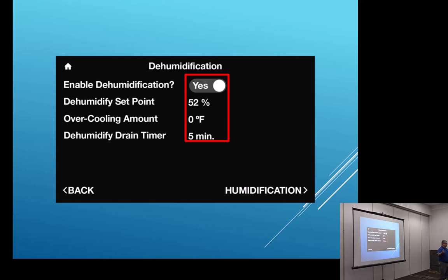Our older systems, we talked about sensible and latent earlier, used to be 75-25, and we're lucky if we're at 85-15 now. So we have less latent heat removal than we used to 20 or 30 years ago in the equipment. They're just not doing as good a job of it. And the systems are sold on energy efficiency, these two-stage and multi-stage units, because they use less electricity at the lower stages. They run longer and use less electricity. Do you think we dehumidify better on the low stage or the high stage?